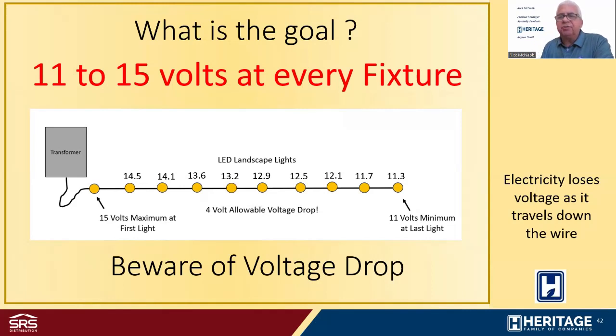And to me, this is probably one of the most important goals on ensuring that this professional outdoor lighting system I'm installing will definitely last a lifetime. And that goal is to have between 11 to 15 volts at every fixture. All LED lights for landscape, all LED lights for professional outdoor lighting will work well if they have 11 to 15 volts. So our goal is to make sure that all the fixtures have that range, 11 to 15 volts. Now, the professional outdoor lighting transformers in the market put out a maximum of 15 volts, which means that there will never be more than 15 volts on any of the fixtures.